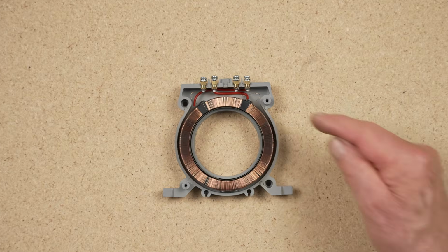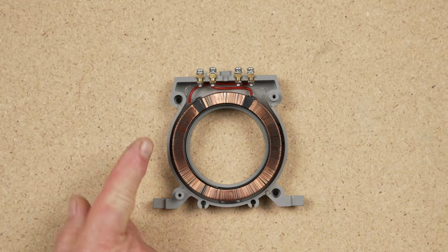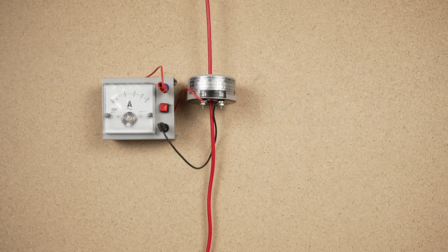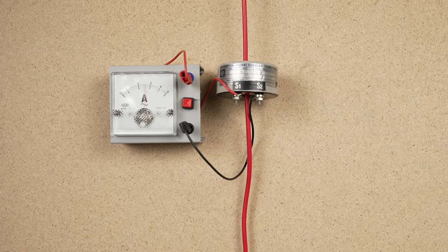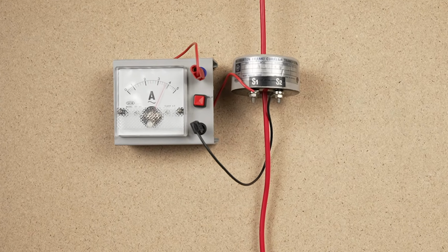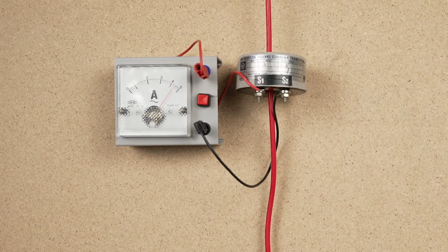The secondary winding of the current transformer is wound around the toroidal core. Depending on the CT design, the full load secondary current will be either 1 or 5 amps when the full primary current is flowing. The secondary winding of the CT is connected to an ammeter designed to read a value of 1 or 5 amps at full capacity. As an example, a 1000 amp CT with a 5 amp output will produce 5 amps in the secondary circuit when the bus bar passing through the centre of the CT is carrying 1000 amps.